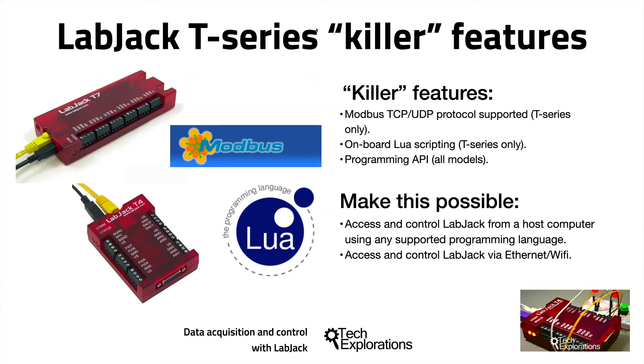Earlier in this lecture, I discussed the features common between all LabJack devices. Over the years, LabJack has added new models with enhanced capabilities. The newer T-series devices include two features that I think are game changers in low-cost data acquisition and control applications. First is the compatibility with the Modbus TCP/UDP protocol, and second, the ability for onboard Lua scripting. Because Modbus is available in the T-series, Ethernet and Wi-Fi connectivity was added. Modbus is important because it makes it possible to access and control LabJack T-series devices via a network.